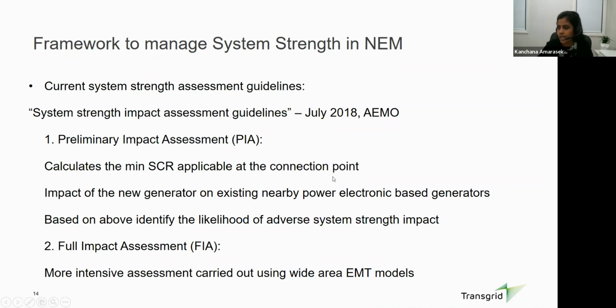So for generators, it shows us a two-stage process. In the initial stage of a generator connection project, the network service provider, or NSP, develops a document called a preliminary impact assessment. In the preliminary impact assessment, we basically look at two things. The first thing is it calculates the minimum short circuit ratio applicable at the connection point of the generator. I mentioned the definition of short circuit ratio: basically, it is the ratio between fault level and the plant MVA capacity. So we are calculating the minimum fault level applicable at the connection point. Actually, in the real calculation, we use a concept called available fault level, but I won't go into those details. But in summary, what it looks at is the minimum fault level and the minimum SCR at the connection point for that connection.